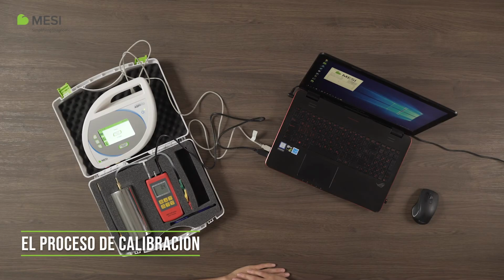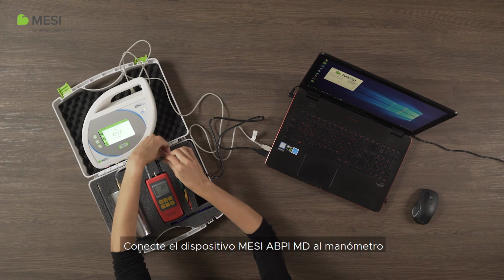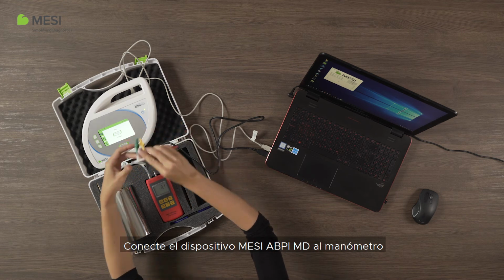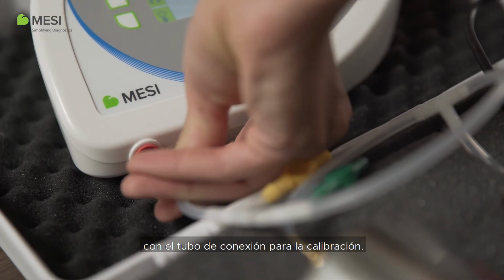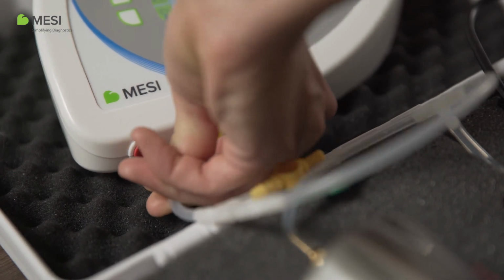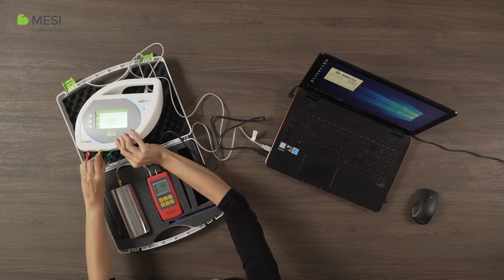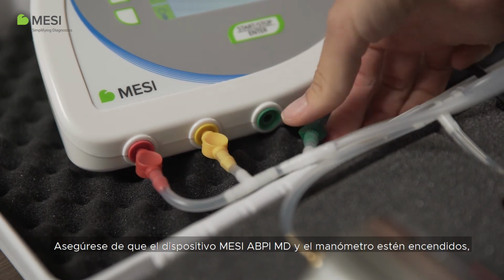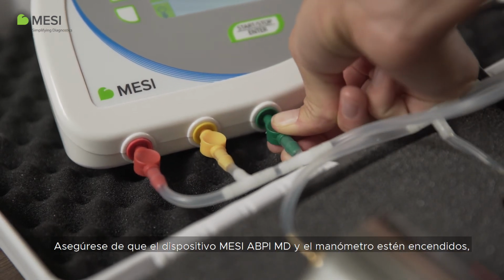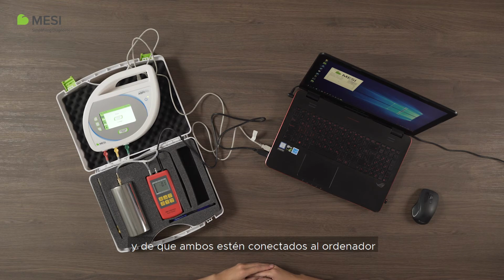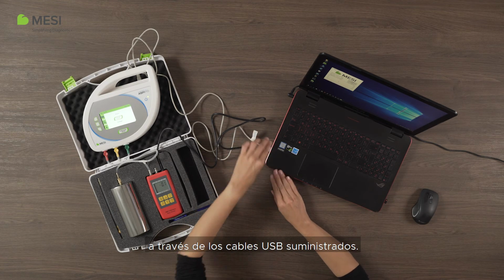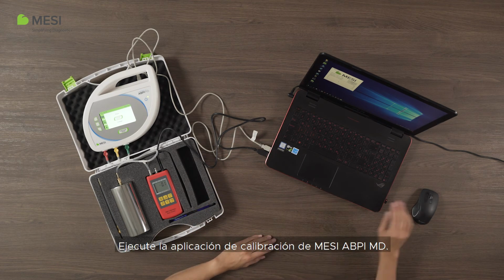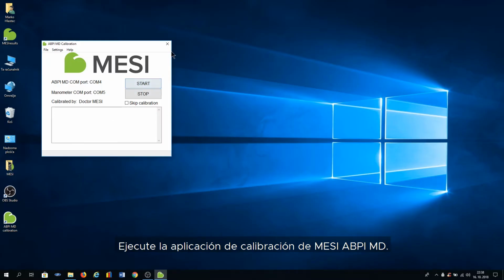The calibration process. Connect the MESI ABPI MD device to the manometer with the connection hose for calibration. Make sure the MESI ABPI MD device and manometer are turned on and that both are connected to the computer via the enclosed USB cables. Run the MESI ABPI MD calibration application. Press the Start button in the pop-up window of the MESI ABPI MD calibration application.